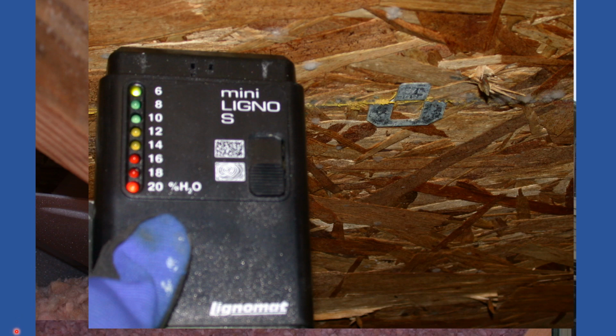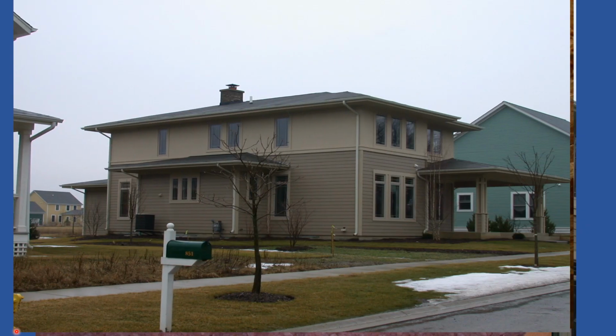So let's go back outside and explain what's happening about that no in but no out. All right, follow with me. Air is supposed to go in, go up like this, and out. Once again, air goes in, goes up, goes out. But that's not happening in this attic. By the way, would you believe this house is only 3 months old? Yep, so what's going on here? Well, the roofing contractor wound up setting that air gun a little too high on power and went bam, bam, bam, bam, bam, and smashed down the continuous roof ridge vent, preventing air from going out. And that's what happened.